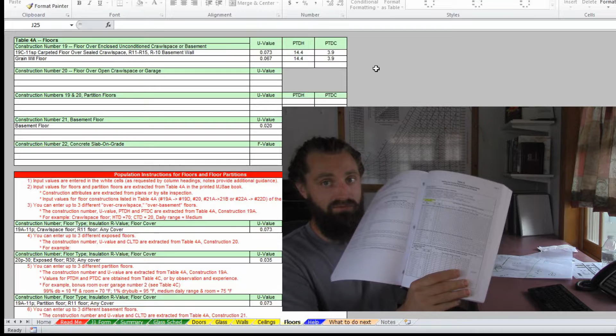If you remember, I have that R10 board insulation on the basement wall, so I went through here and I'm in construction number 19C. I go down, find that I've got an R13, so I used the 11 just to be safe - loose fill or blanket, and it is in a sealed attic, not a vented attic or crawl space, it's a sealed crawl space. So I go across, find a U value of the floor of 0.073, then go across and find our design temperature difference for the heating - 14.4. Good, so that is that.